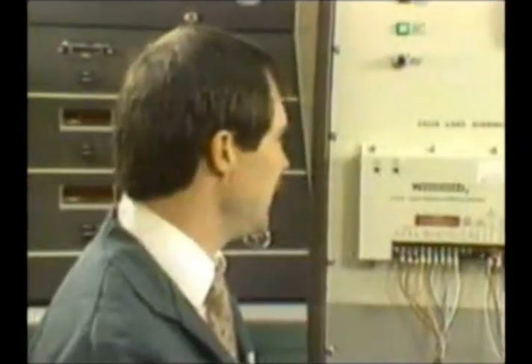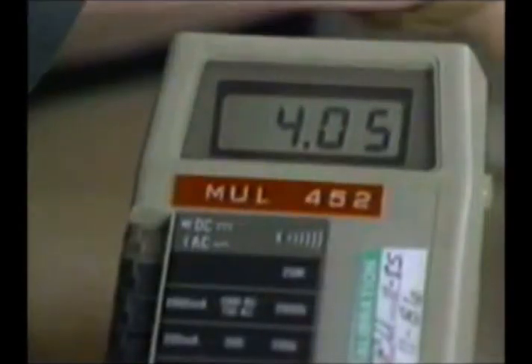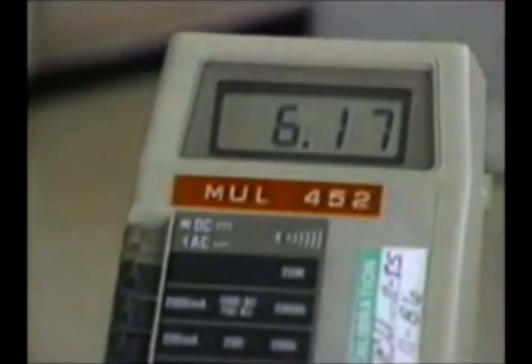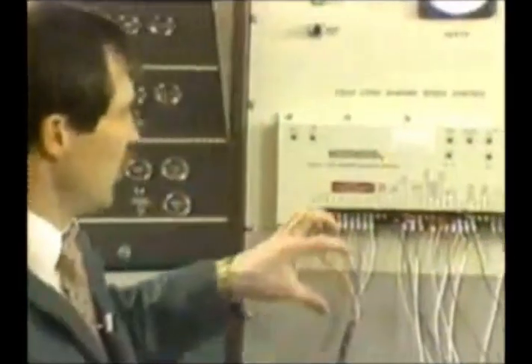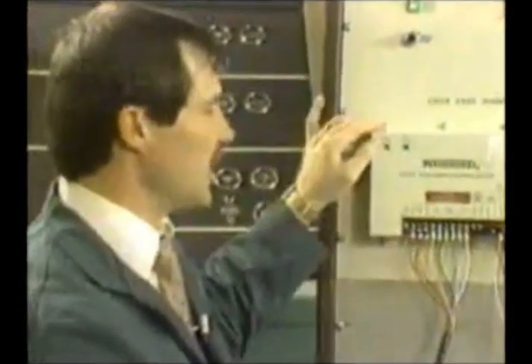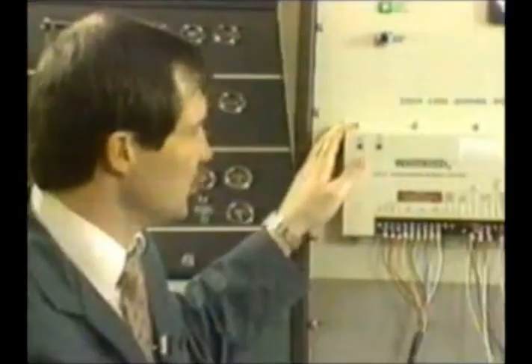Come right up to rated speed. Now as I load up, you'll see that we're going to read just above 6 volts at full load. Now that we're set up for full load, went over load gain voltage, need to talk about droop. I haven't used my circuit breaker auxiliary contact yet. Right now that's open, and we've been running in droop, except it's been 0% droop.